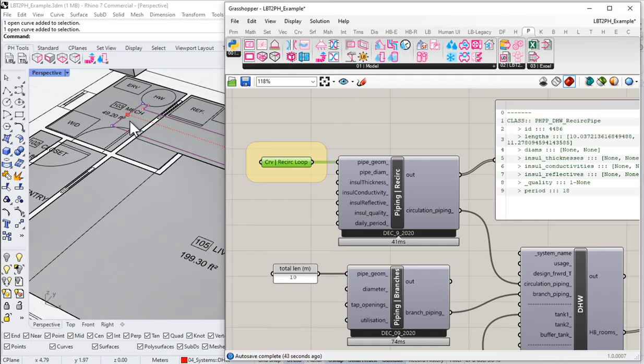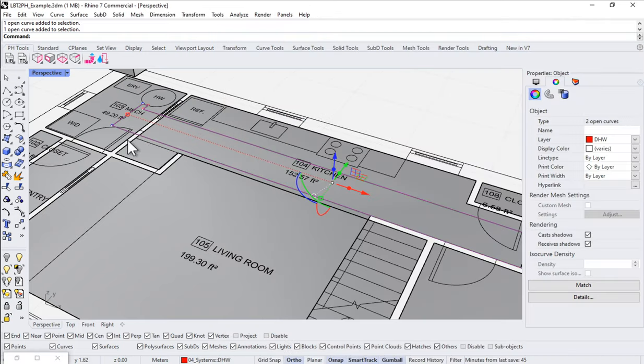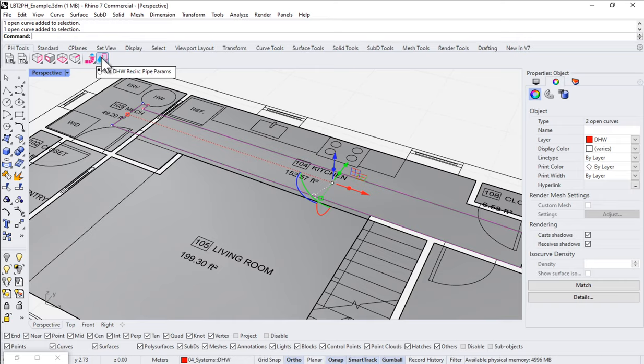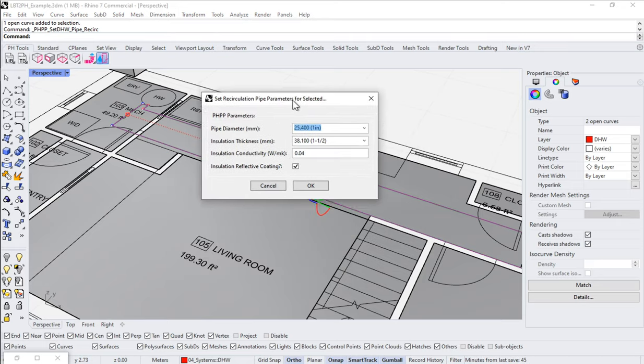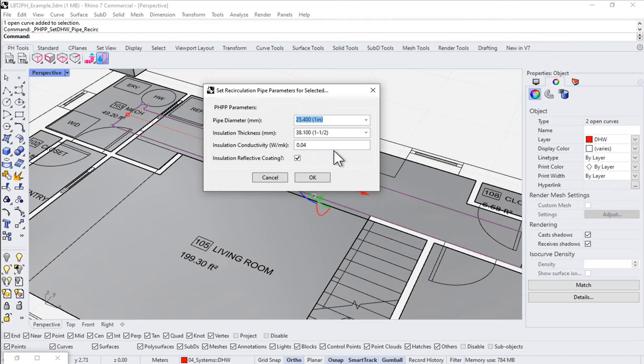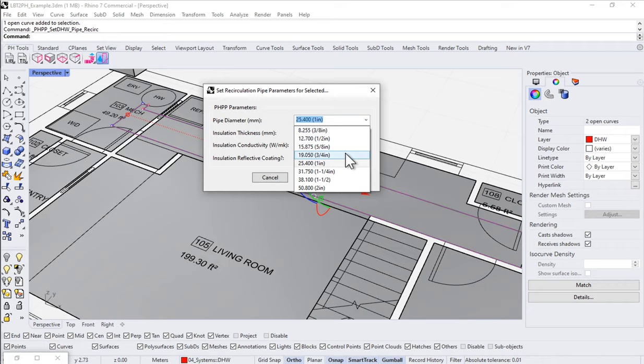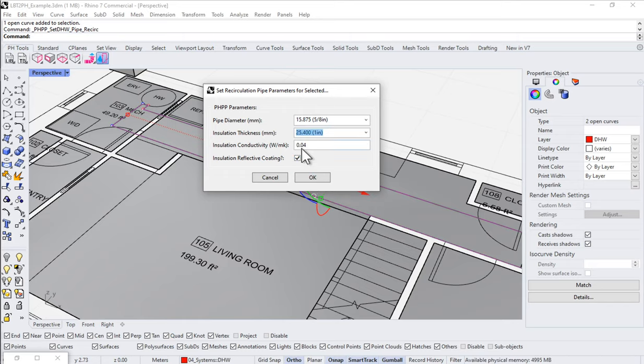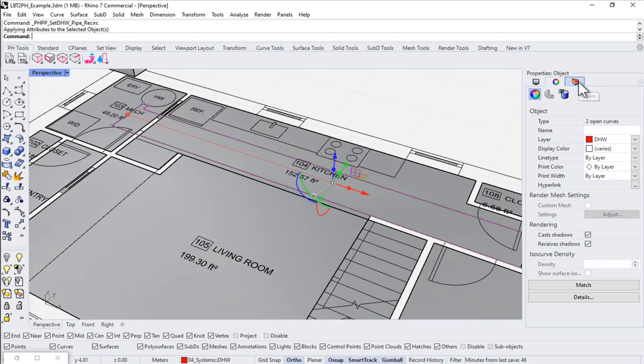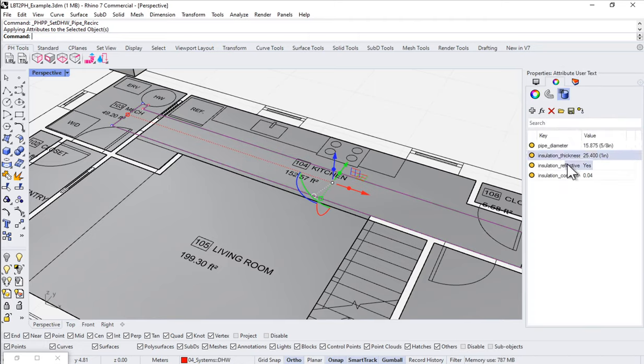We can assign that information. With my curves selected back in Rhino, if you come up to the PH Tools ribbon and come over to Set Domestic Hot Water Recirc Pipe Parameters, we can assign parameters to those curves — things like pipe diameter, insulation thickness, insulation conductivity, and whether the insulation has a reflective coating. For a house like this, let's say the recirc loop is five-eighths of an inch, insulated with one-inch insulation, fiberglass insulation, and yes, it has a reflective coating. I'll say okay.